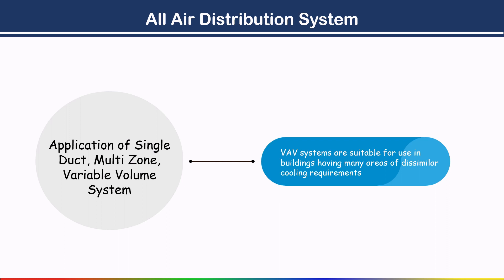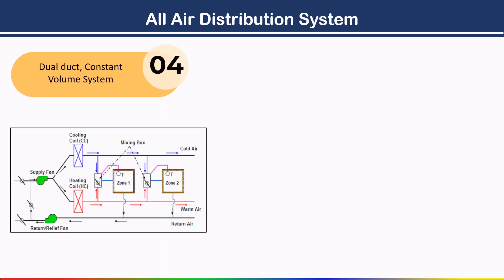The fourth and final type of all-air distribution system is the dual duct system — dual duct constant volume or variable air volume system. Two ducts are used: one to supply conditioned (cold) air to each zone and one to supply warm air to each zone. Because two ducts are used, this system is called a dual duct system.